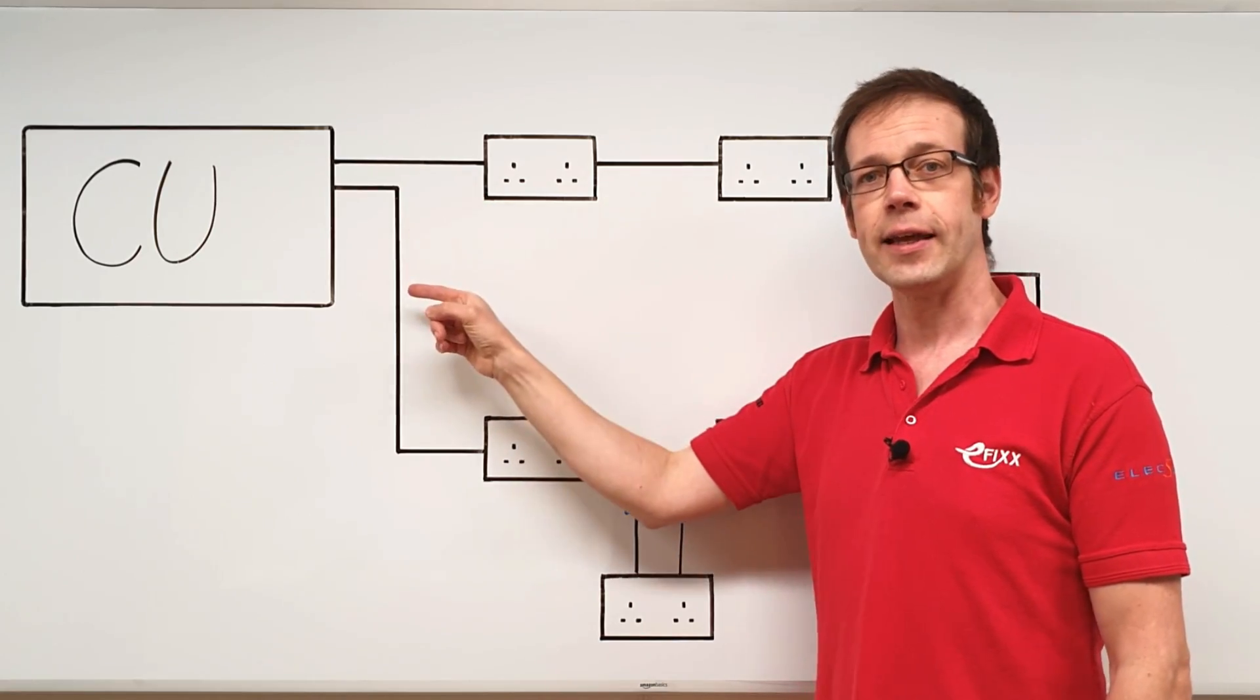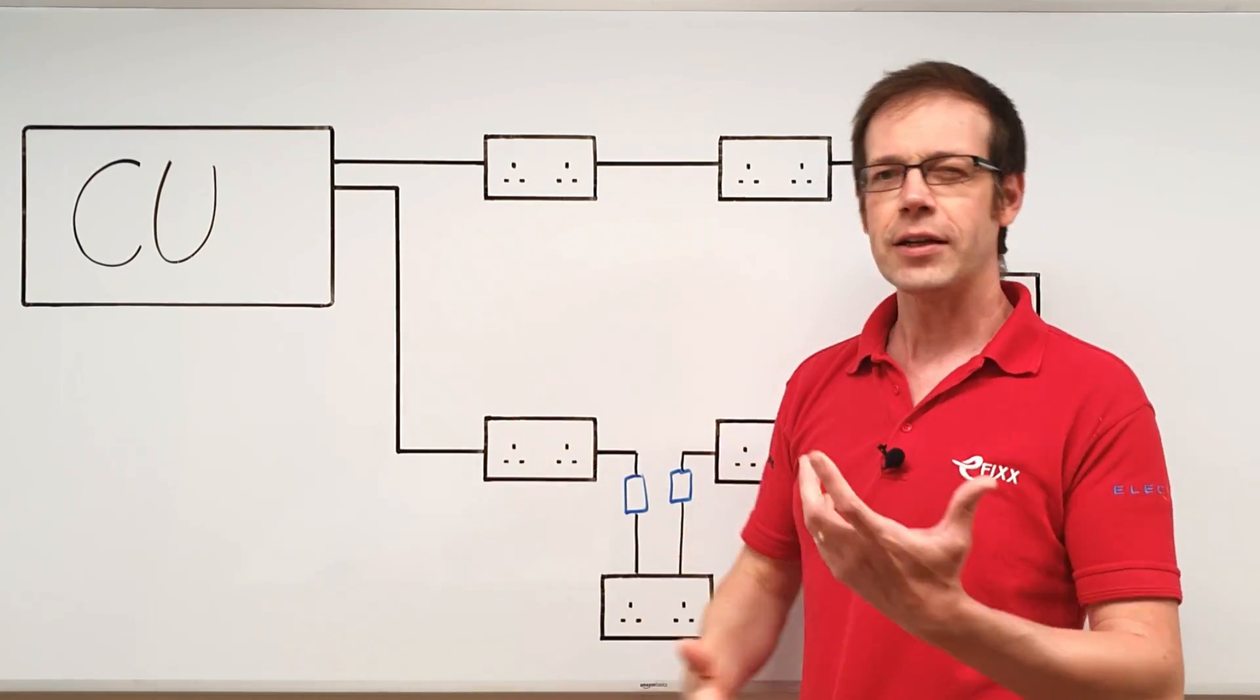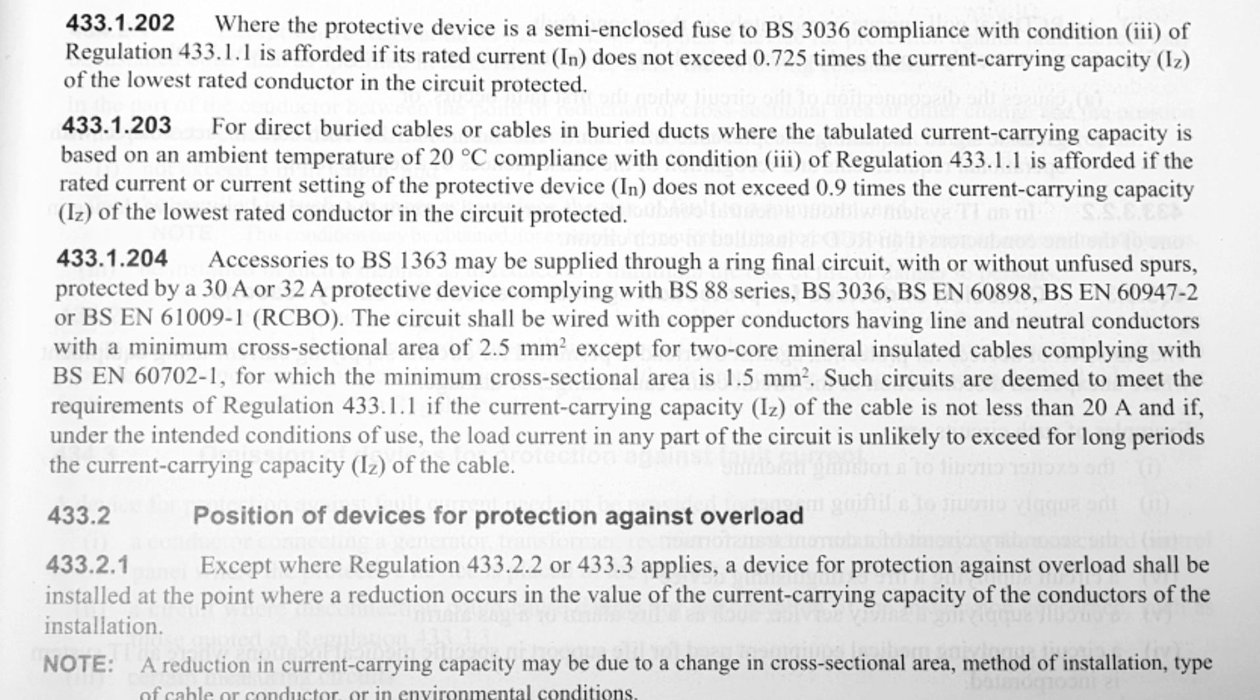This fact is acknowledged and allowed for in Regulation 433.1.204, where it states—and I'll just highlight the key points here—accessories to BS 1363 may be supplied through a ring final circuit protected by a 32 amp protective device. The circuit shall be wired with copper conductors having line and neutral conductors with a minimum cross-sectional area of 2.5 millimeters squared.